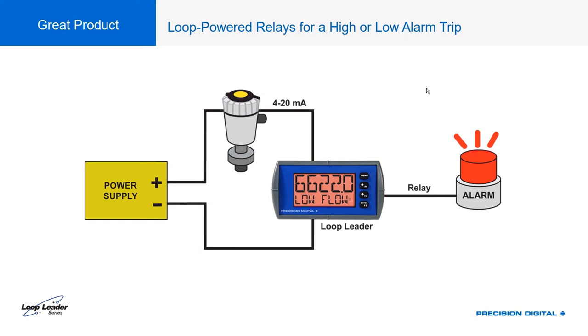Although the Loop Leader is a loop-powered device, its relays allow it to go beyond just displaying information next to a tank. Those relays can directly drive equipment or drive external control relays to set off sirens, send signals to PLCs, or turn on light stacks. This makes it more than a display — it's a controller — and it's generally lower cost than a four-wire or externally powered equivalent device.